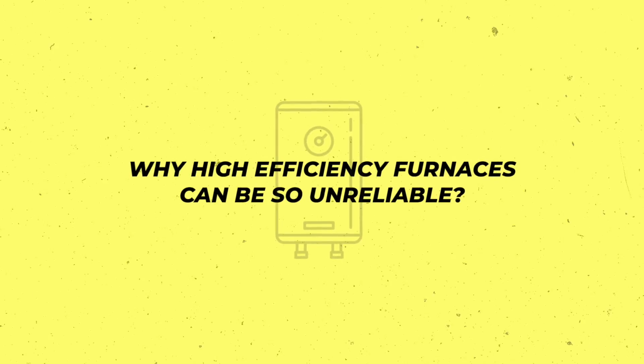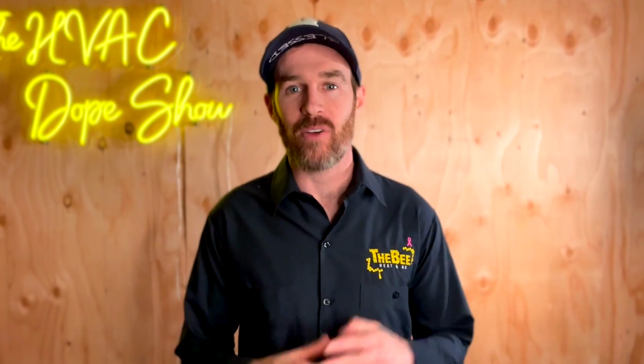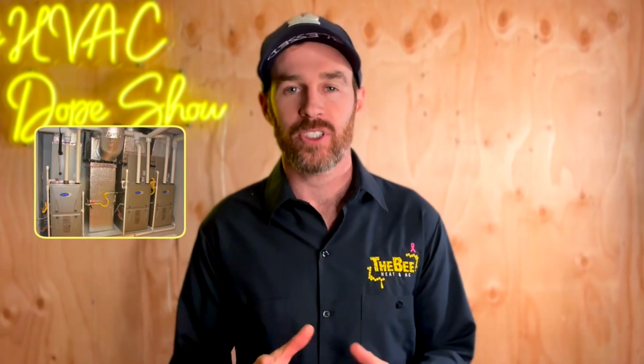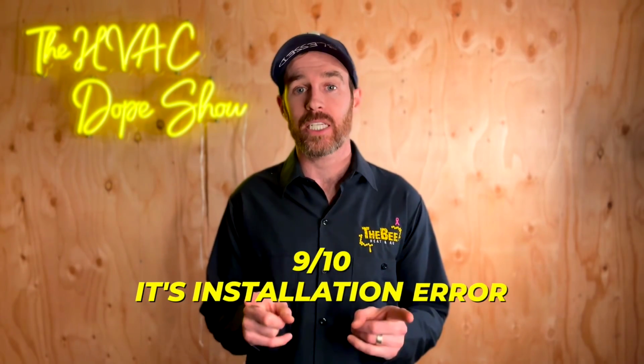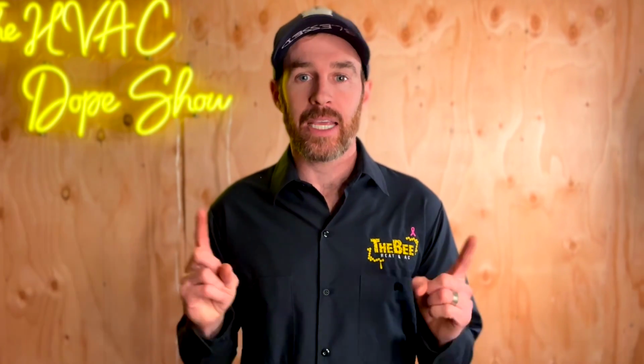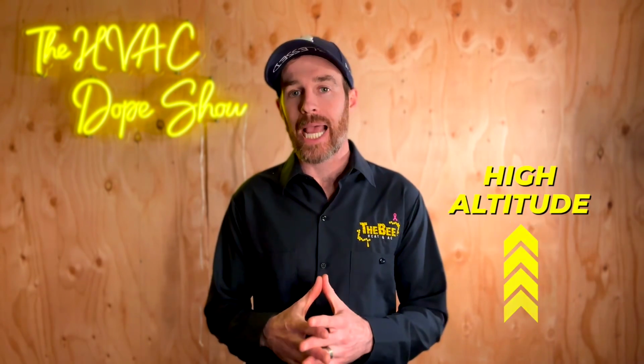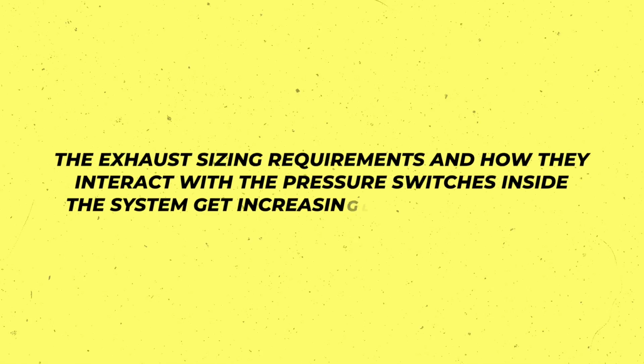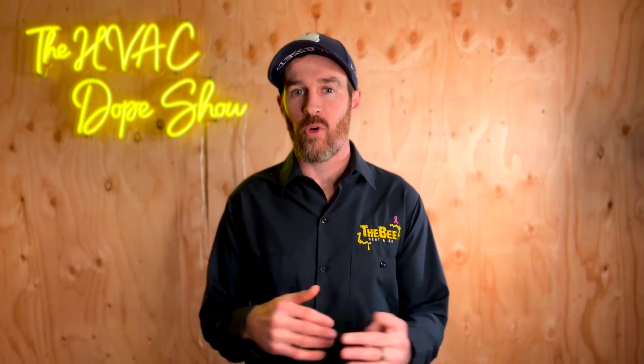In this video, we're going to talk about why high efficiency furnaces can be so unreliable and some of the most common causes to check for if you're ever having issues. The truth is, as much as I hate to admit it, every time we are having issues with a high efficiency furnace, 9 times out of 10, it's installation error, because although these are more efficient than your standard 80% furnace, they can be finicky if they're not installed properly. And this is especially true at high altitudes because the exhaust sizing requirements and how they interact with the pressure switches inside the system get increasingly more demanding. But we will talk about all this and more in this video.